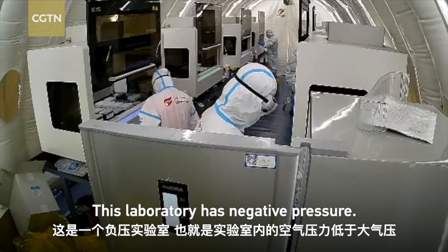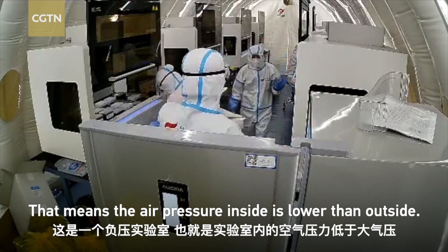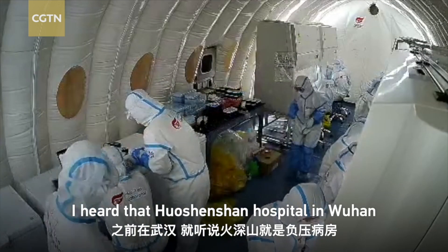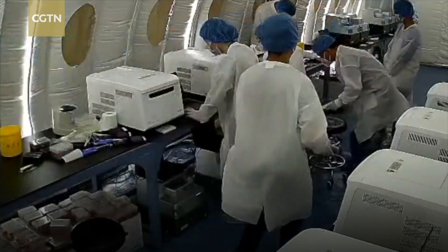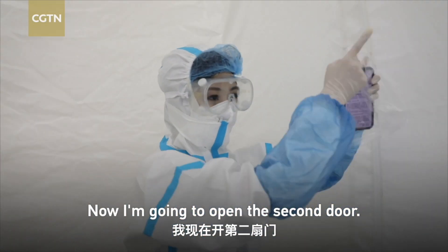This laboratory has negative pressure. That means the air pressure inside is lower than outside. Air flows inward, so it cannot contaminate the world outside the lab. I heard that Huoshenshan Hospital in Wuhan had negative pressure wards, and I was always curious what it's like to be in there. I can clearly feel the wind flowing in. Now I'm going to open the second door.